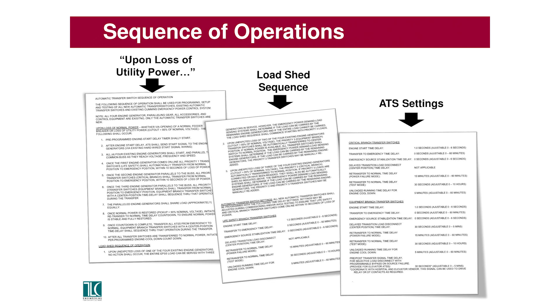All we're looking for is something that starts with, upon loss of utility power, the following shall happen. And hopefully the design team has thought that through. Especially with bigger, more complex systems - multiple generators that get into load shedding schemes - there's real importance in how the transfer switches are programmed and what those time delay settings are, both for switching to emergency power and switching back. You probably don't want an entire hospital block loading onto the generators all at once; you might want to stagger that big pie chart of equipment load, do that in pieces. So that's all we're looking for: sequence of operations.